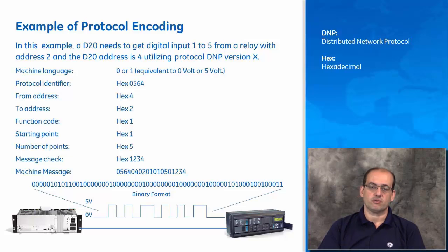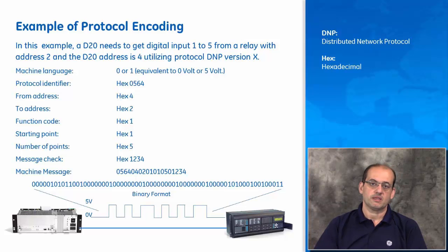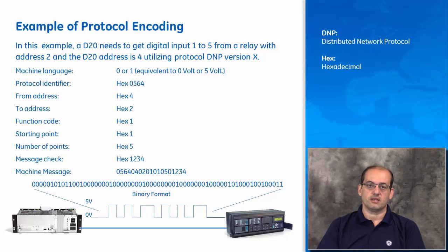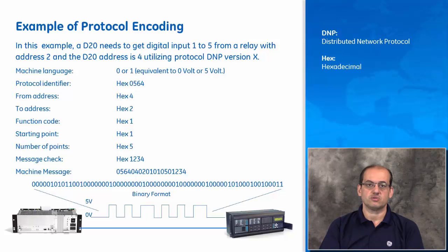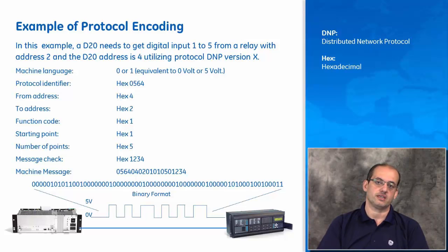Every message also contains a cyclic redundancy check (CRC) — a mathematical formula that calculates the message integrity. So in this case, that full message in hex would be: 056404020101501234. This hex message is then translated into machine language — 1s and 0s transmitted over the wire using voltage sensing levels of 0 to 5 volts — and translated at the other end from voltage levels into bits and bytes into a meaningful message for the device to take the appropriate action.